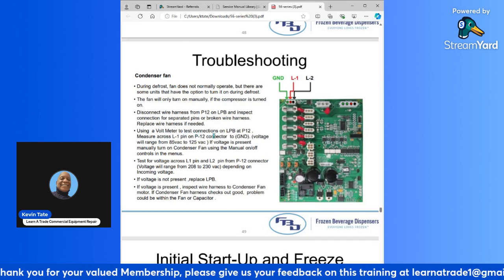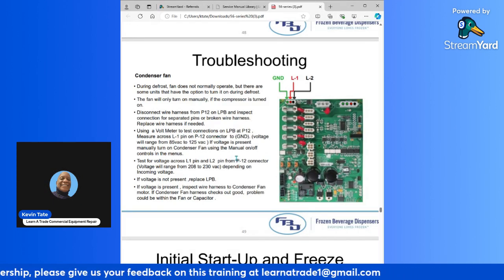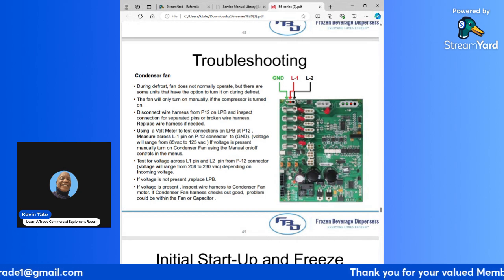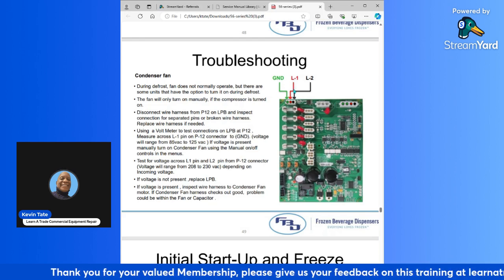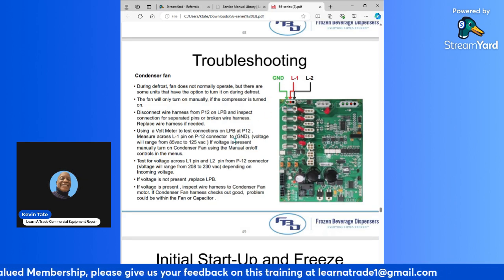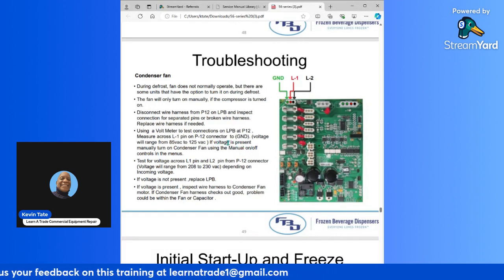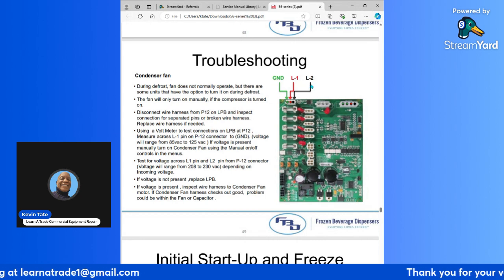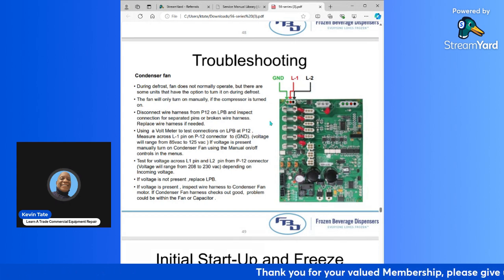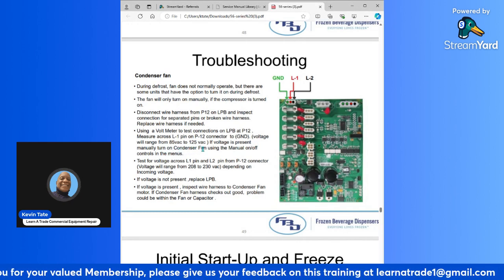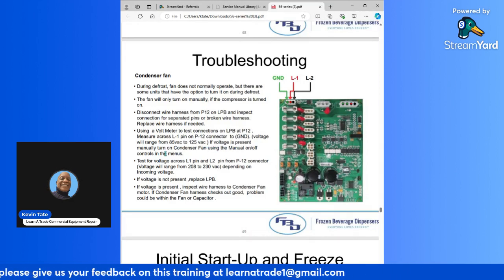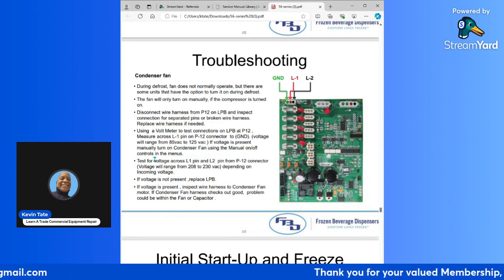Using a voltmeter to test connections on your lower board at P12, measure across the L1 pin and P12 connector. This is your L1 pin, and this is your P12 connector. Okay, this is your ground, and then this is your L2. So you would check across these two pins. Voltage will range from 85 volts AC to 125 volts AC. If voltage is present, manually turn on the condenser fan using the manual on and off that's in your service menu.